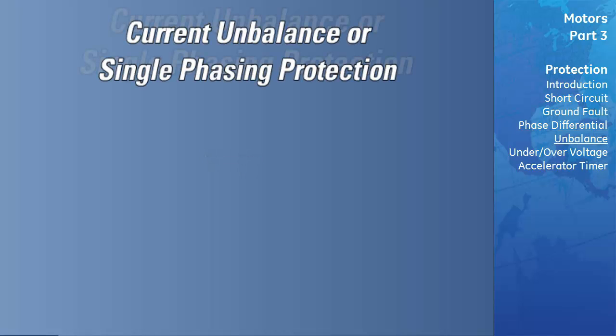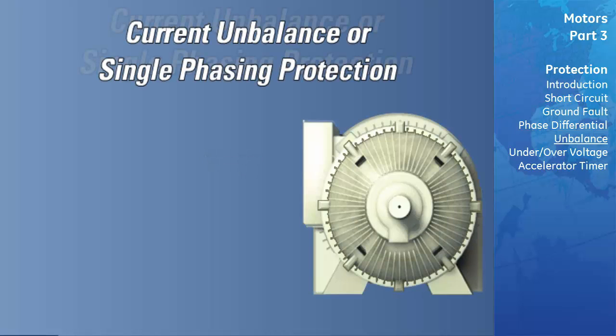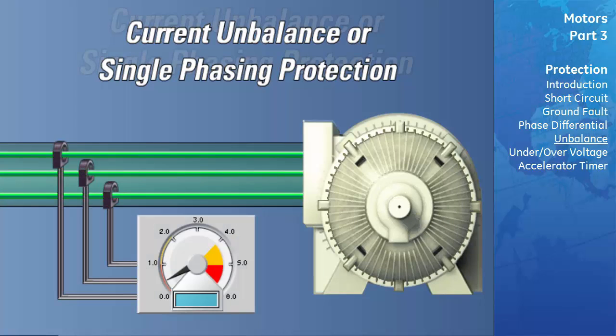Current unbalance or single phasing protection. The contribution of current unbalance to the thermal capacity used was covered earlier. Here, the magnitude of the current unbalance is used to detect and trip the motor if a single phase condition occurs. Single phase refers to the situation when one of the three phases is no longer being supplied to the motor. If enabled, a trip and/or alarm occurs once the unbalance magnitude exceeds the current unbalanced trip pickup for a period of time specified by the current unbalance alarm trip delay.